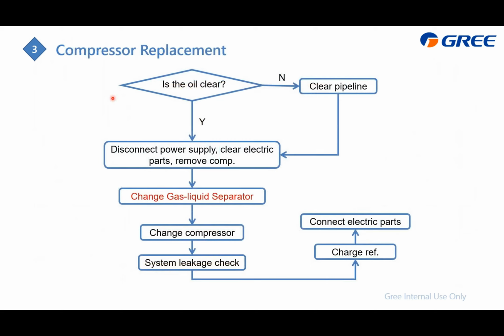Back to here, if you find that the oil is not clear, you need to clean the pipeline and also the inside components. It is really a tough job. And after that, it's the same as when the oil is clear: disconnect the power supply, clear the electrical part and remove the compressor. And you can also find out whether the oil is contaminated or not. We still recommend changing the gas liquid separator. And after that, change the compressor, do the system leakage check, charge the refrigerant, and connect back the electrical parts.